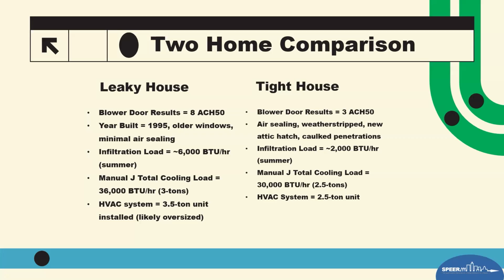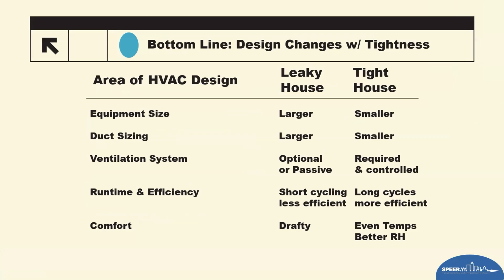And then we'll talk about, at the very end, kind of an HVAC checklist to say we need to verify this. All of this is acceptable to go through, but if the sizing is correct, then the home meeting that Manual J has been done as well. So bottom line, design changes with tightness. Equipment size: if you have a leaky house, you have larger equipment. Tight house, you have smaller. It changes the ducts also. You can have smaller duct systems, or you can eliminate duct systems altogether. If you have a very tight house, you can use a mini split.